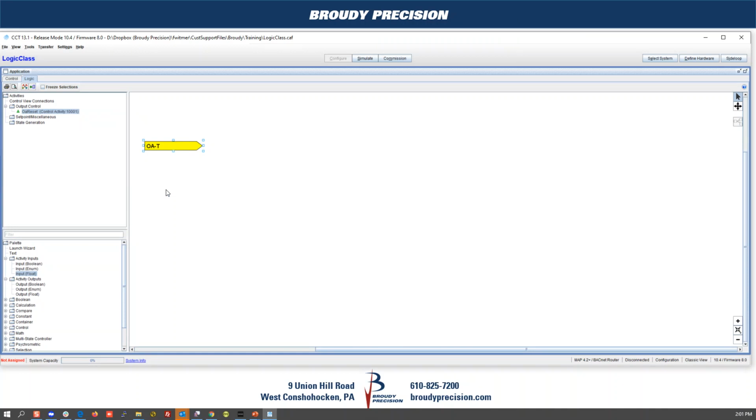And then we also need our 4 settings for the reset, so we know how to control. What we basically want to do is take outside air temperature, between 35 degrees and 65 degrees, and we want to have our hot water set point be 180 degrees down to 120 degrees. So we need to add some more of these floating inputs.